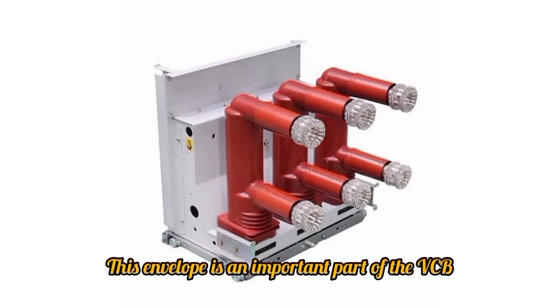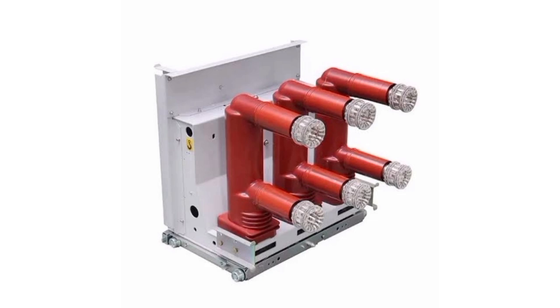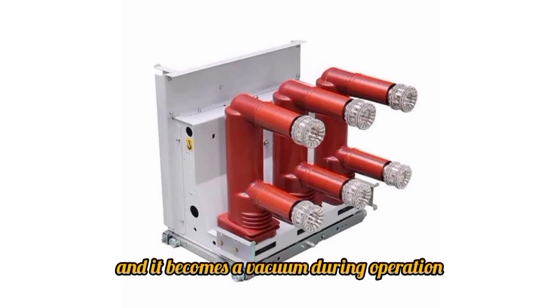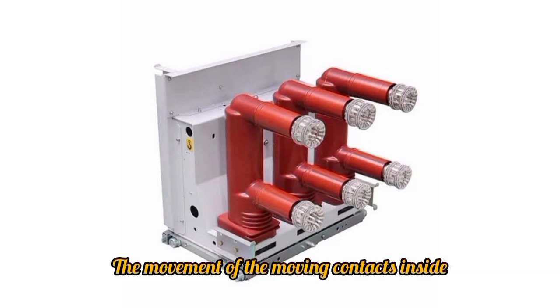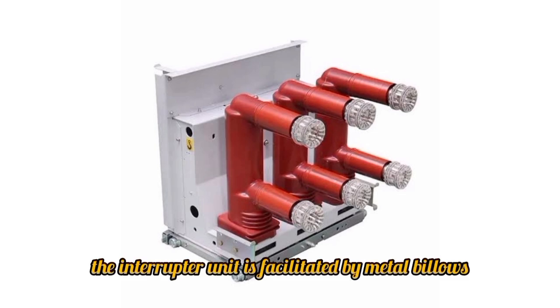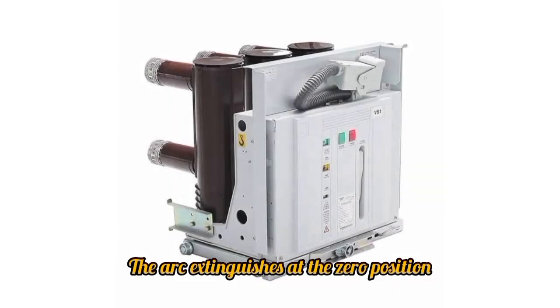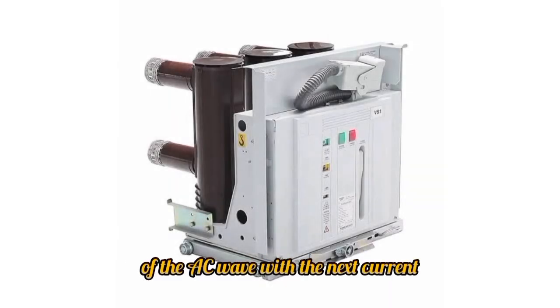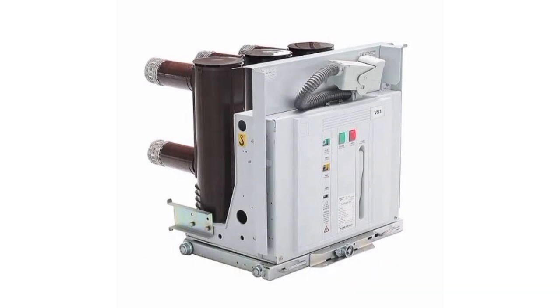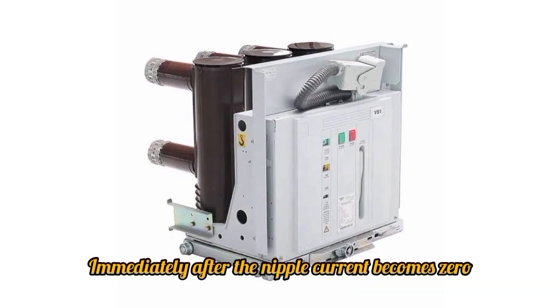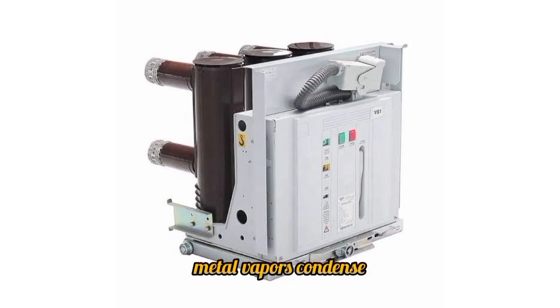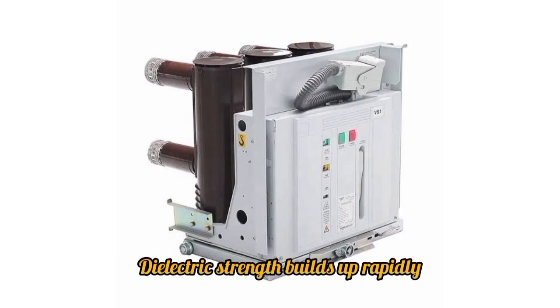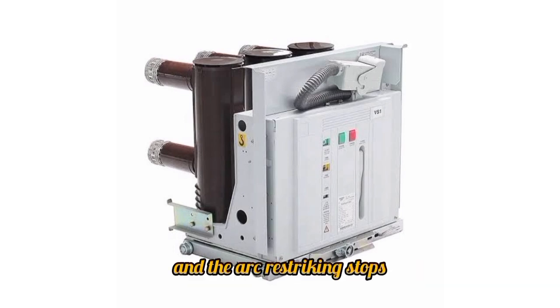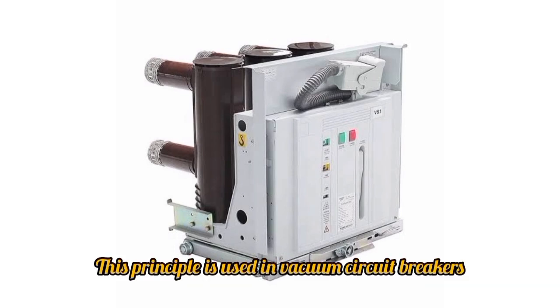This envelope is an important part of the VCB, and it becomes a vacuum during operation. The movement of the moving contacts inside the interrupter unit is facilitated by metal bellows. The arc extinguishes at the zero position of the AC wave with the current. Immediately after the current becomes zero, metal vapors condense. Dielectric strength builds up rapidly, and the arc restriking stops. This principle is used in vacuum circuit breakers.